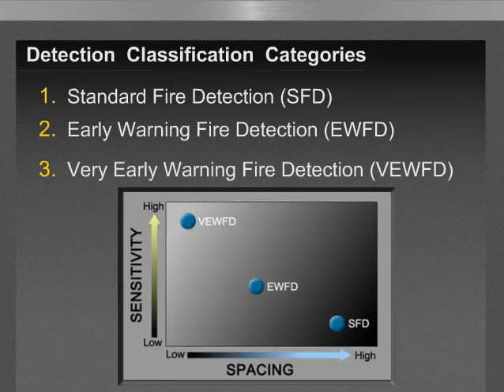All right, so as we look at detection classification categories, there are essentially three sensitivity classifications used by the industry. They are standard fire detection, early warning fire detection, and very early warning fire detection. Parameters regarding each classification are primarily defined by sensitivity and spacing. So here on this chart, we've shown diagrammatically the relationship of the various sensitivity classifications as they lie on the chart. And so as we see spacing as being much less dense for standard fire detection, it would follow the sensitivity is lower for standard fire detection. And conversely, as we look at very early warning fire detection, sensitivity being high, very sensitive, and with spacing being much more condensed, less spacing between each device.